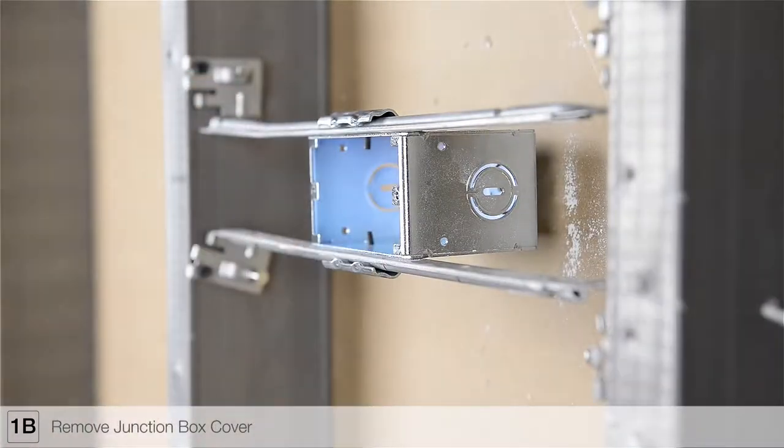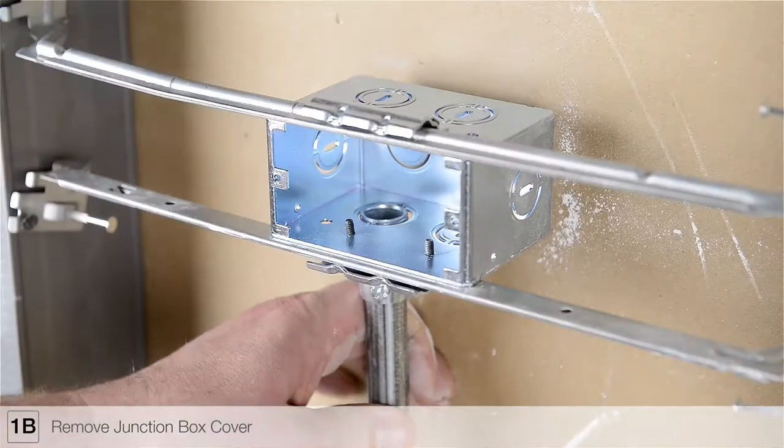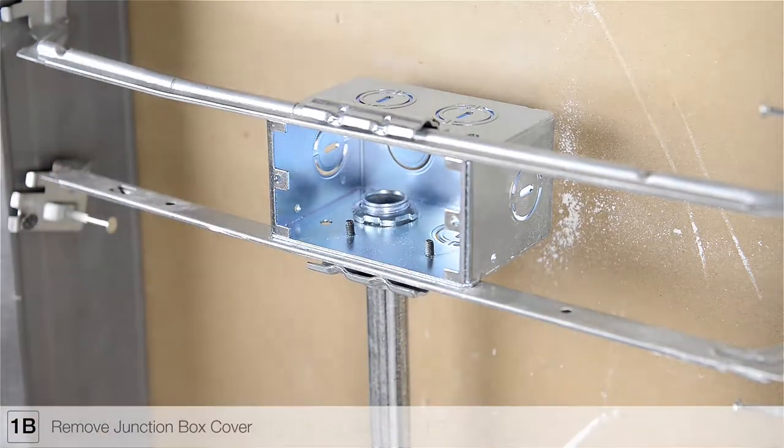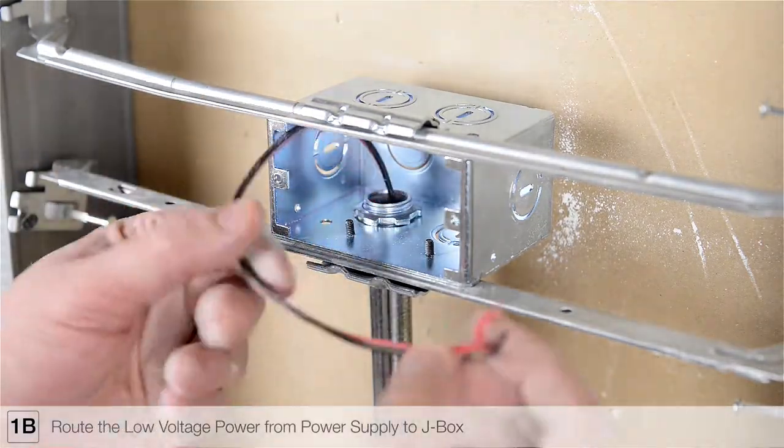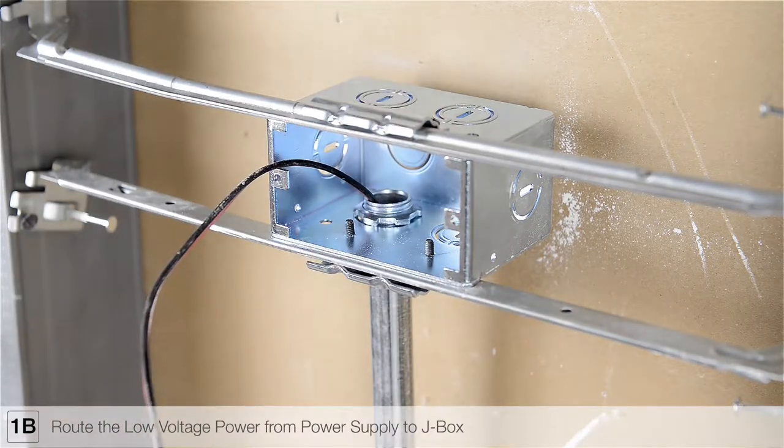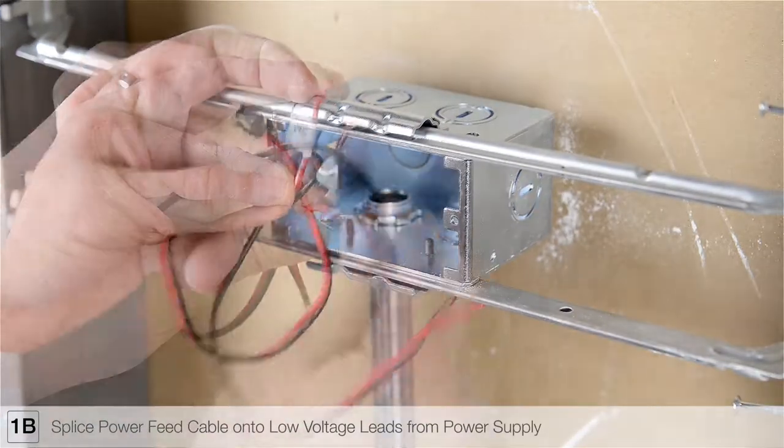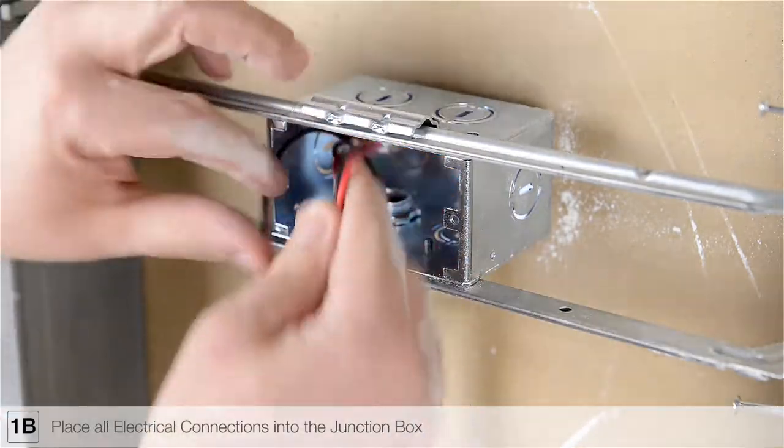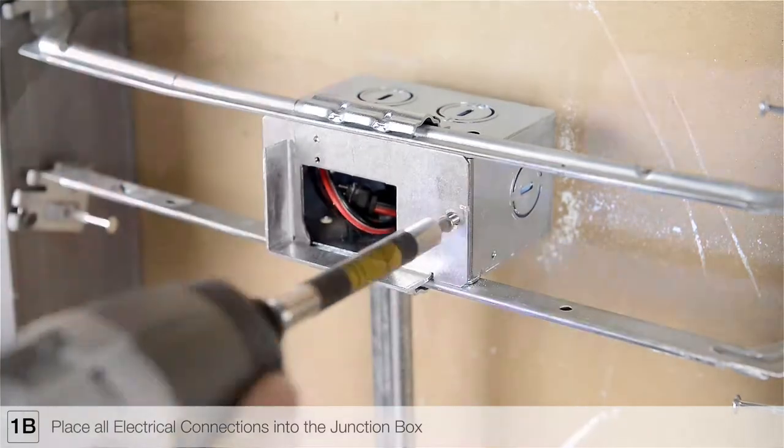Remove a knockout from the power feed junction box and, if required by your local electrical code, install conduit. Route the low voltage power wires from the remote power supply to the power feed junction box. Splice the included power feed cable to the low voltage power wires using wire nuts. Place all electrical connections into the junction box.